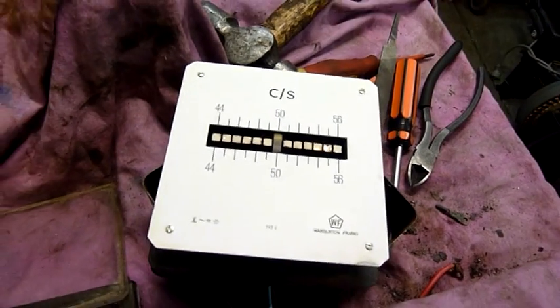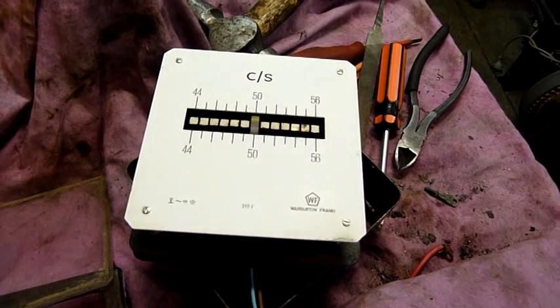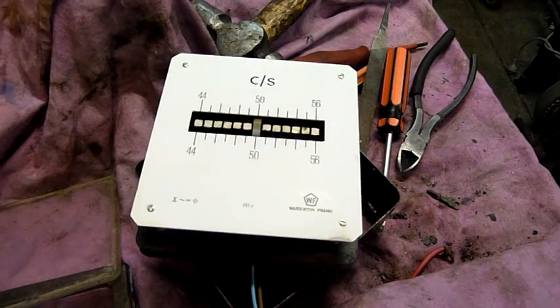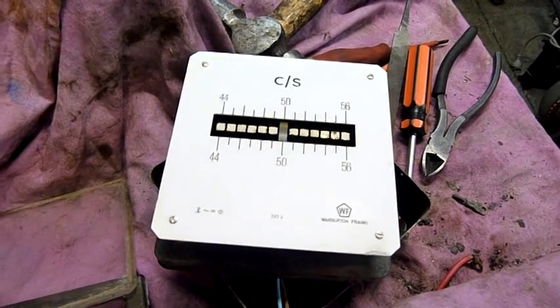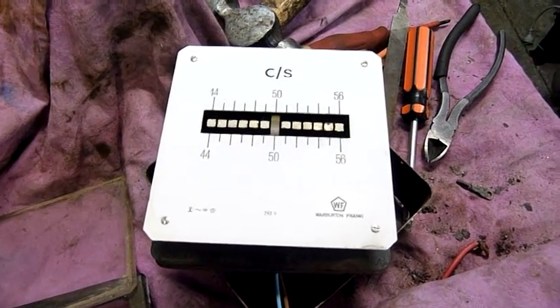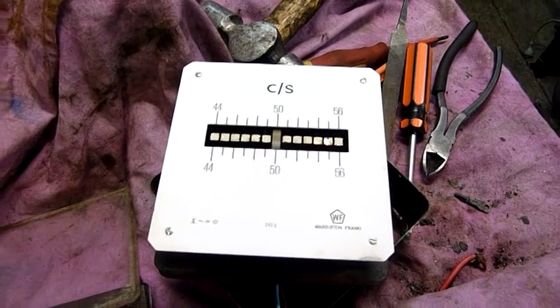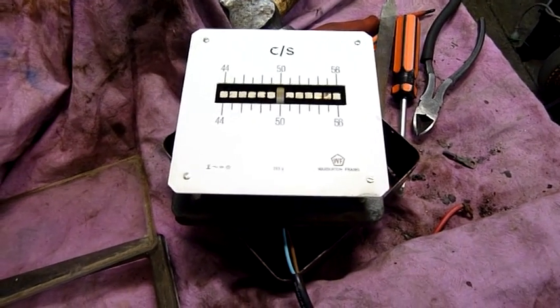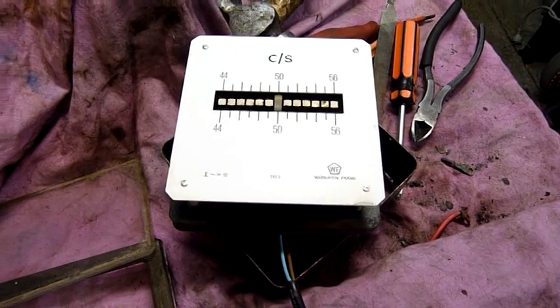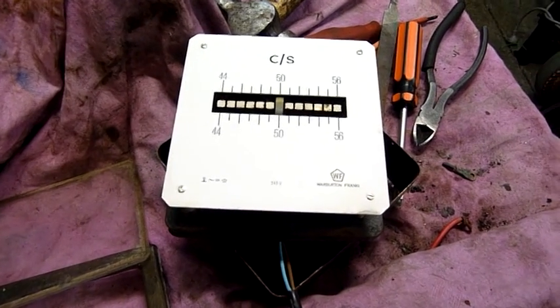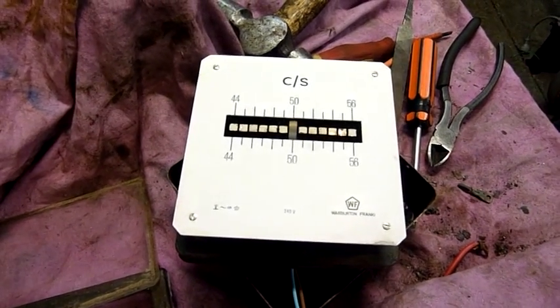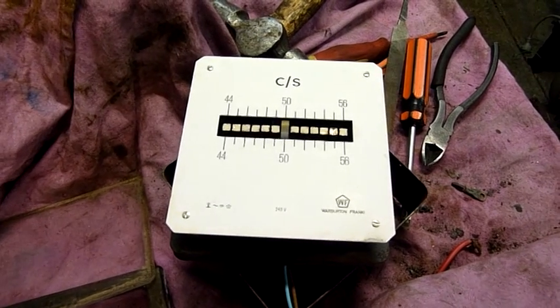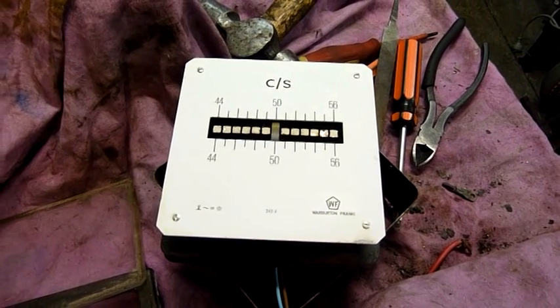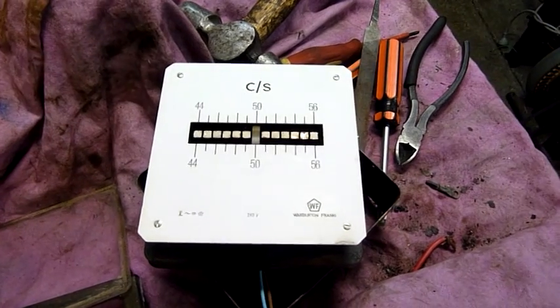Should connect this thing up to the Lombardini diesel and the China one eventually when I get the good starter motor. It'll be a good way to calibrate the output frequency and set governors. It's how you set the governors on generators like that, like normal alternator type generators. Set it at no load, 52 hertz, then put it under load and see if it drops below 49.